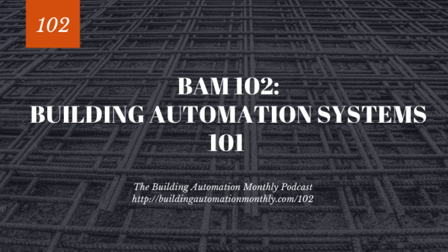So, building automation servers. The main reason we have these is to combine multiple supervisory devices into a single user interface. That's the main reason for a server. There's analytics software out there that can pull directly from a supervisory device, so it's not necessarily going to need a server to do analytics. Sometimes you'll hear folks say you need a server to do analytics, but in most cases you don't. If you want to pull multiple supervisory devices together though, you're going to need a server, whether it's cloud, physical, or hybrid - doesn't really matter.